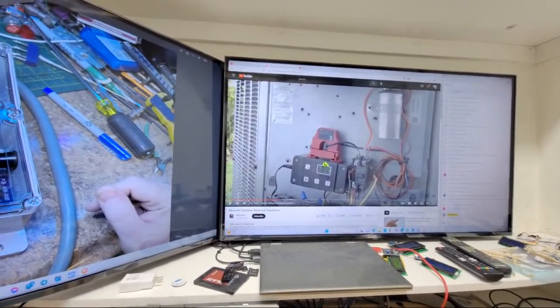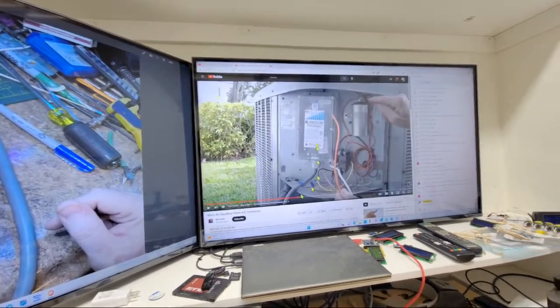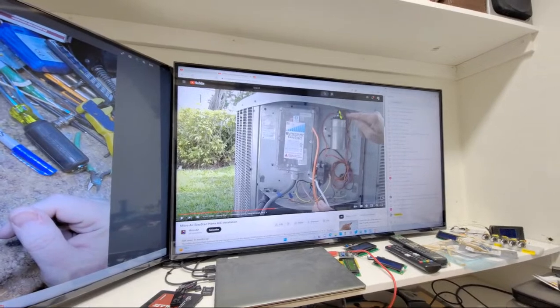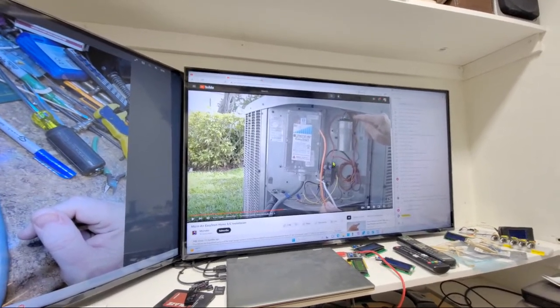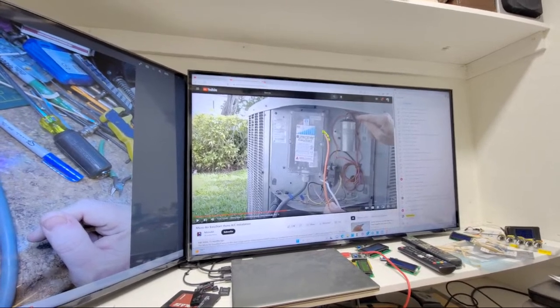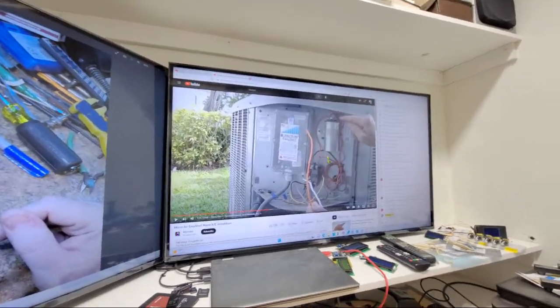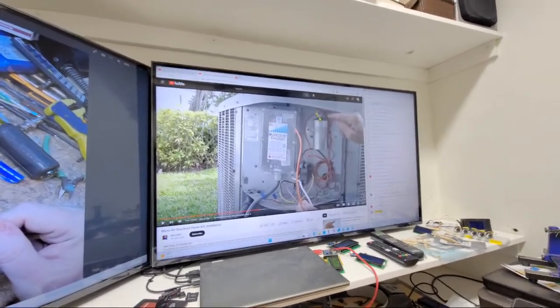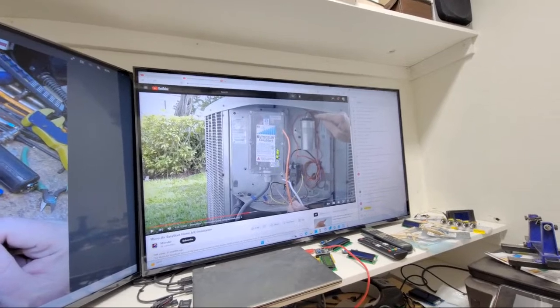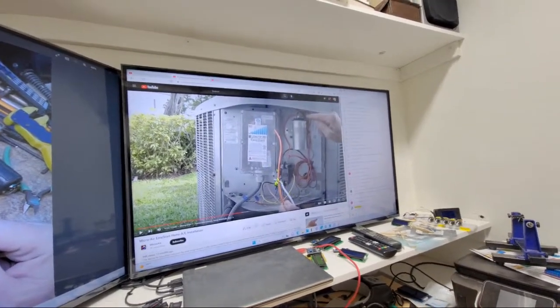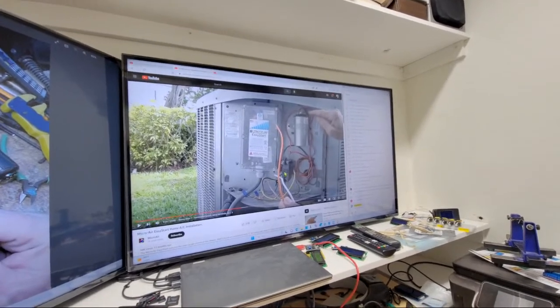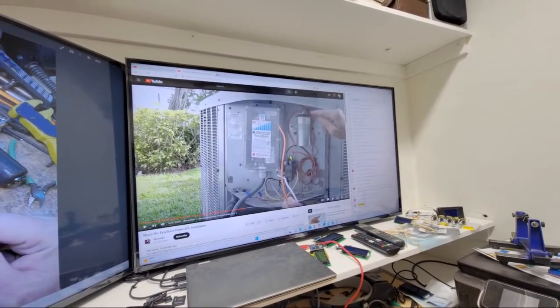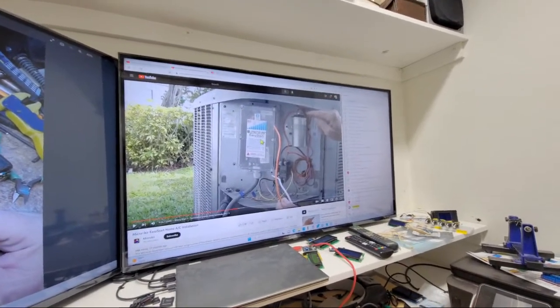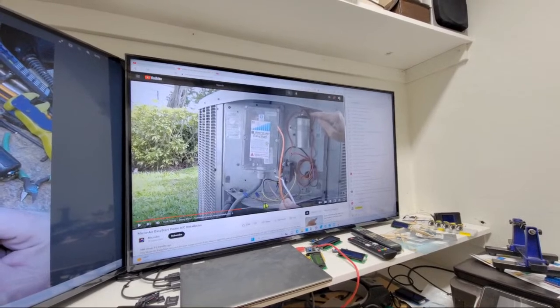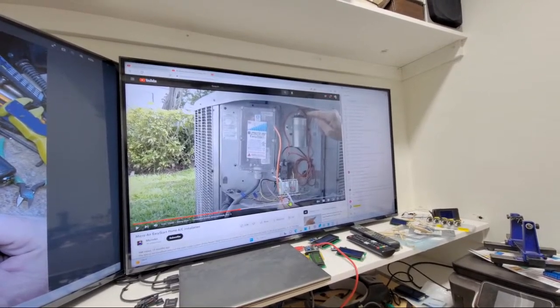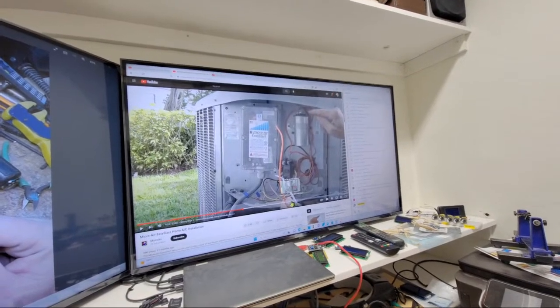So that's fine. So they're going to go and install this thing, which they install in here, and basically I noticed that they're pulling off the run wire, and so the wire's going to go in here and then come back out, and that's how they're delaying the compressor. And then they're also adding a wire to the start cap because it's going to connect to this start cap, electronically in here, and doing stuff like that. So what's happening after they install this is when they push this contactor in, you immediately get the power to your outdoor fan like normal, but then this thing adds a little delay, and then it starts up a little quicker. So let me see if I can find where he's got his after. He's getting ready to stick his pen in there or whatever.